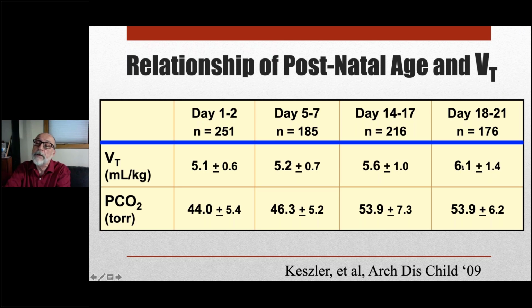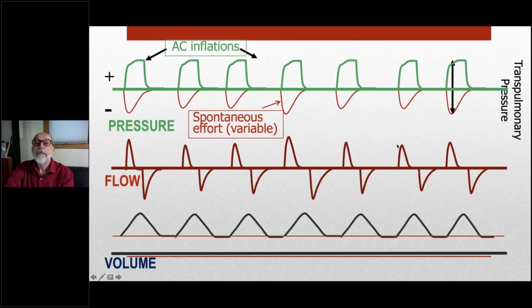Some babies might be okay with 5. Depends on the degree of alveolar dead space again, because these babies do begin to develop some air trapping and overexpansion. But it's important to keep in mind that what we don't see on the ventilator interface is the patient's spontaneous effort. And this is just an example of one set of curves. So this is the standard pressure, flow, and volume curves.